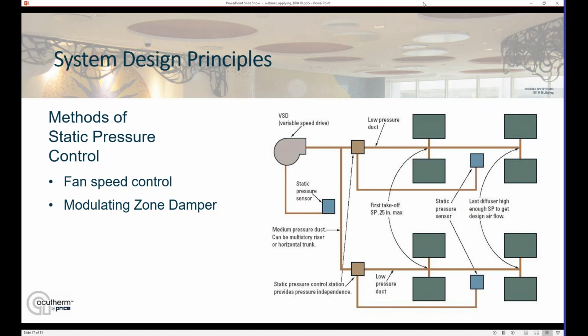In the medium pressure portion of the ductwork, in that drawing there, these might be 2 floors of a multi-story building, and that's the riser between them. But you'd locate another static pressure sensor there. Now, as multiple of these modulating zone dampers start to close down, the fan can slow down by maintaining the pressure in the medium pressure section of the duct. So you're still achieving good energy savings by slowing down the fan. We're just using that medium pressure to distribute around the building over the longer distances, and then dropping to low pressure amongst the diffusers.